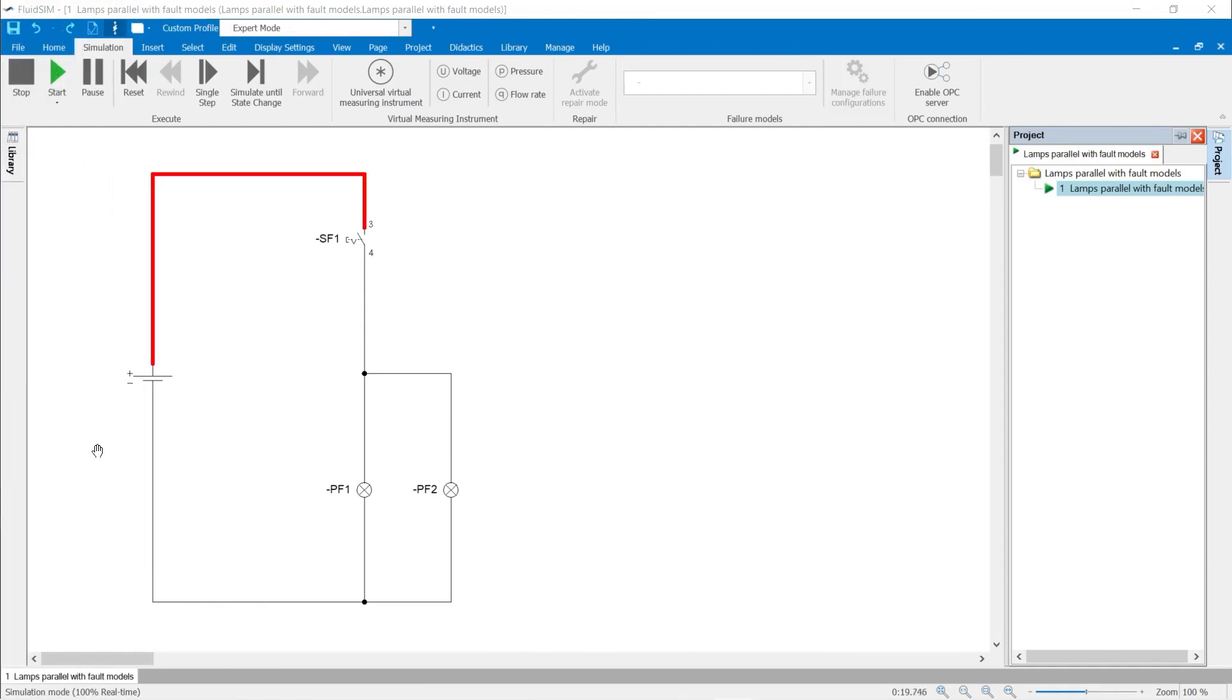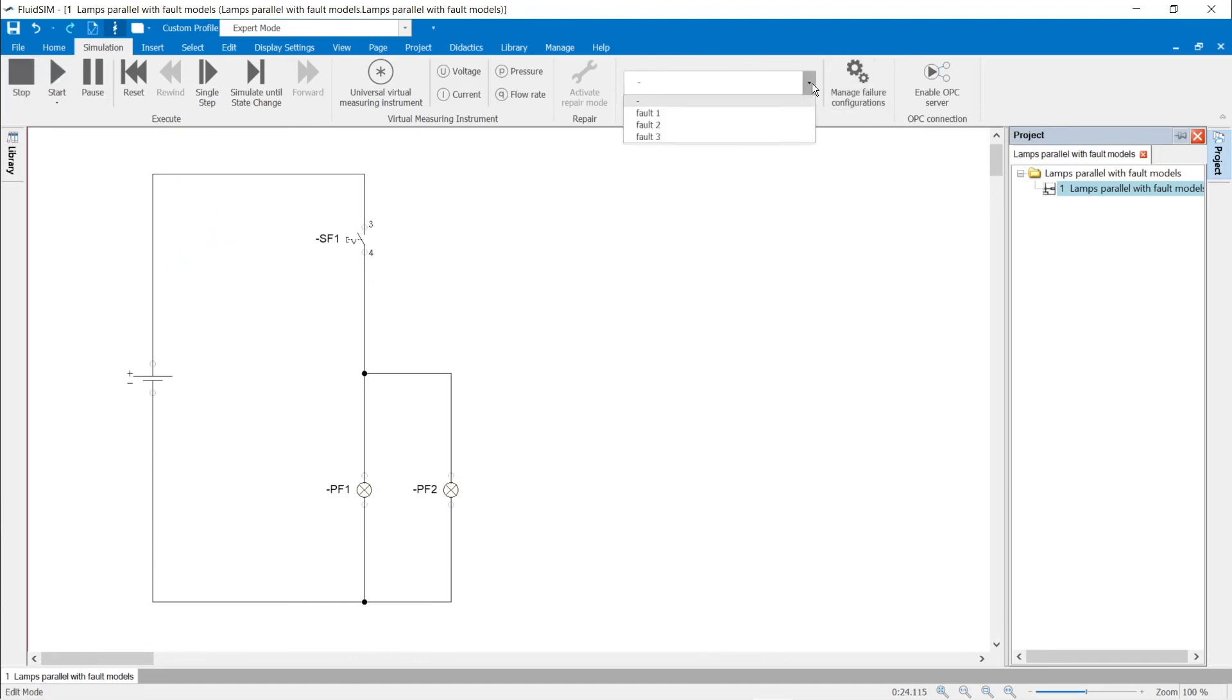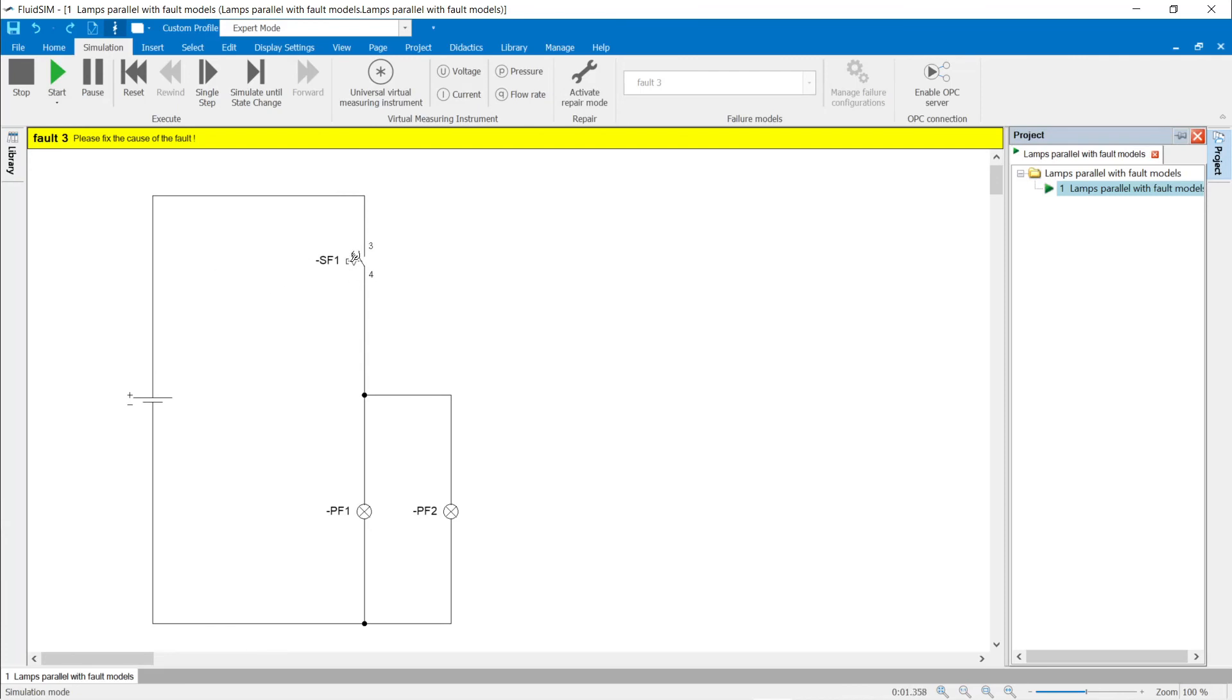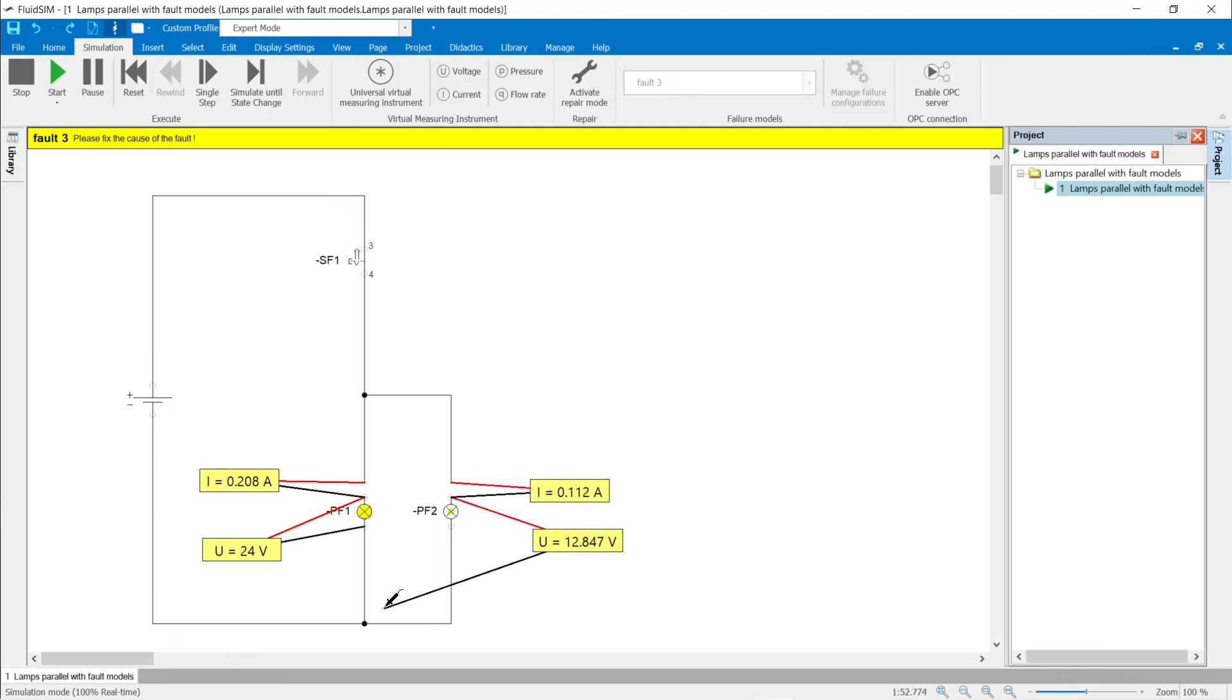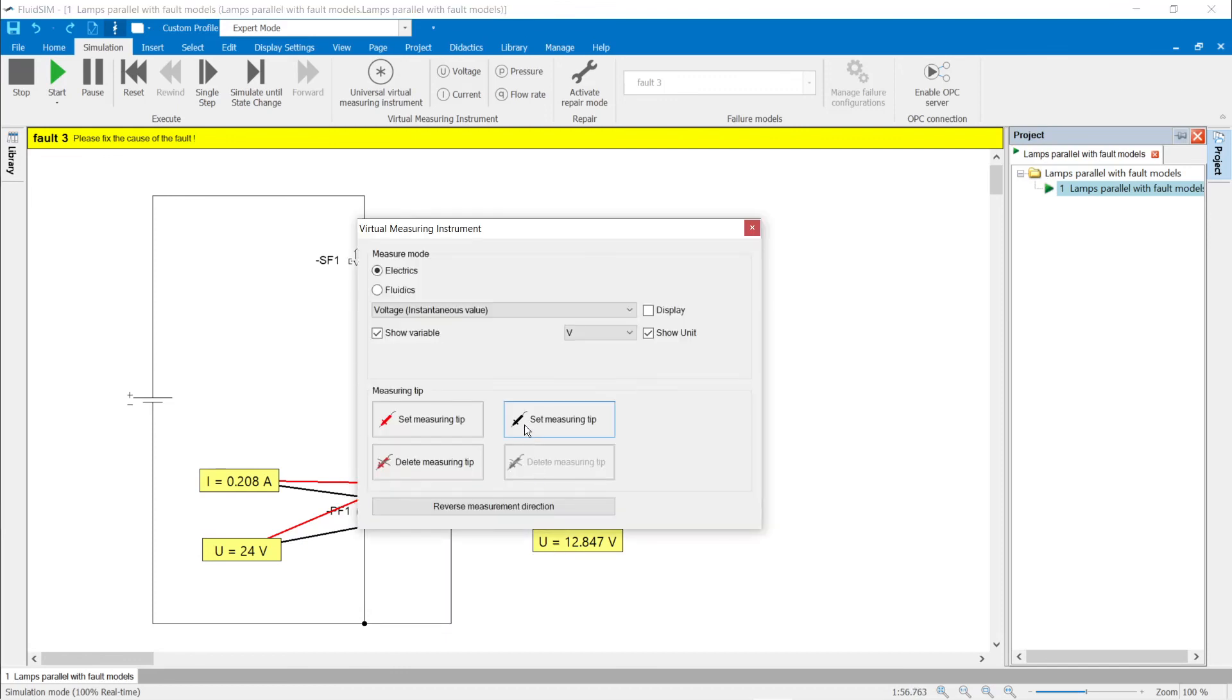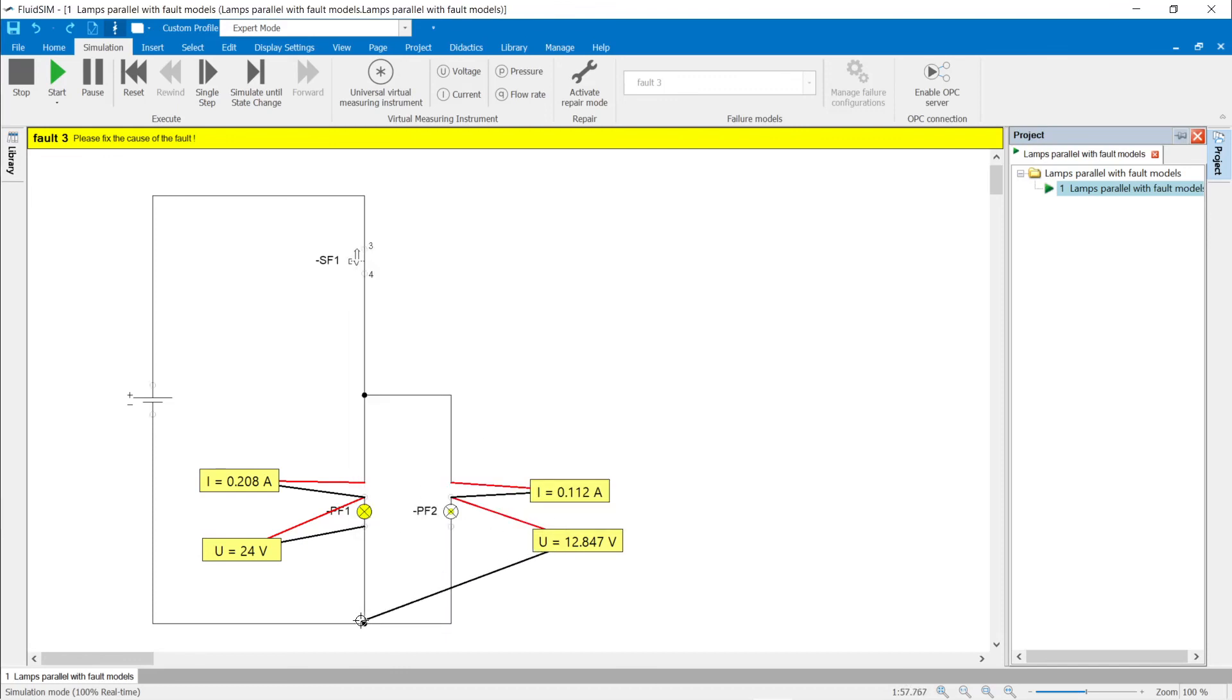Failure simulation: parameterizable failures. Failure 3 is selected and the simulation started. The lamp PF2 only lights up weakly. The voltage at lamp PF1 is 24 volts and at lamp PF2 is 12.8 volts. The currents through the lamps are also different. If you measure the voltage on lamp PF2 compared to the ground connection of lamp PF1, 24 volts are displayed. The line connection from lamp PF2 to the ground point must therefore have an increased line resistance.